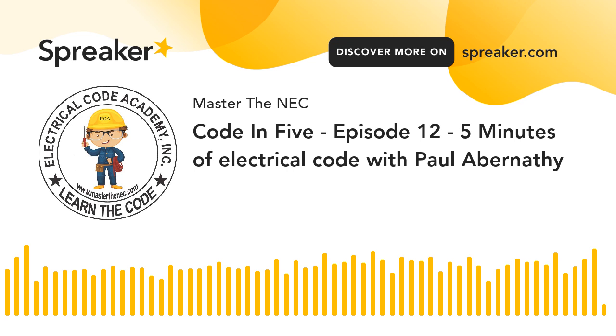Now, what we want to talk about is the uses not permitted. For example, it says it's not to be installed where exposed to physical damage. That's 336.12, item number 1. Number 2 says, look, you cannot install tray cable outside of a raceway or cable tray except as permitted in 336.10(4), which was on a messenger, 336.10(7), which is from the cable tray to the equipment, that unique application, 336.10(9), that's the one for use in 1 and 2 family dwellings, and then, of course, 336.10(10), which is direct burial.